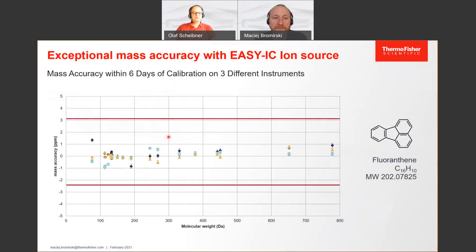If we look at how this works, here we have data from three different instruments in three different parts of the world, where we looked into the mass distribution over a six-day course. You see that no matter which mass you're looking at — we have one calibrant mass at 202, but wherever the mass you want accurate is, it doesn't matter. It works over the whole mass spectrum and over the full six days. So there is very good instrument-to-instrument reliability, and you have constant mass accuracy better than 1 ppm for a long time.